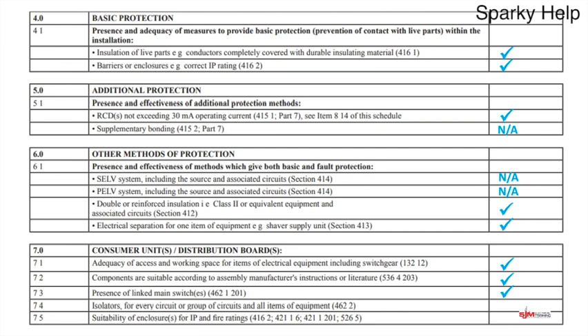We don't have to think about it because the manufacturers tend to put a double pole switch in. When you buy three-phase boards, it's the main switch you'd normally have to specify, because you want the current rating, but you might want a 4-pole or you might want a 3-pole depending what happens to be, so that might not be so standard when you order that.